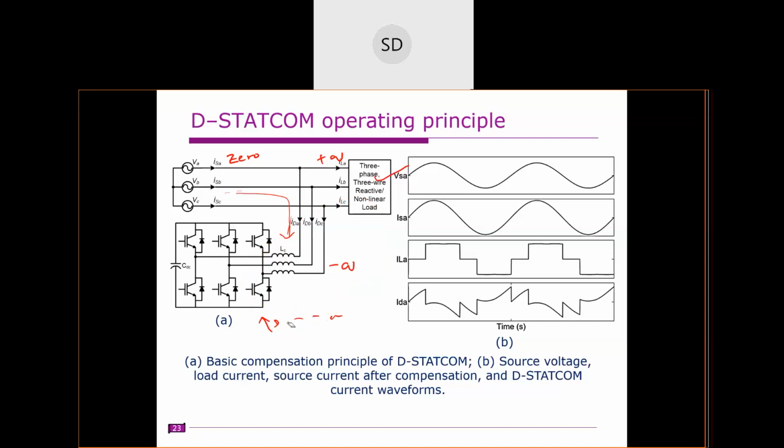So the STATCOM ideally only draws reactive power, but in the practical case we have these switching devices, and they have some losses. These losses are always real power losses. We already discussed that, so there is no need to connect a DC source here. A small energy storing capacitor is sufficient.